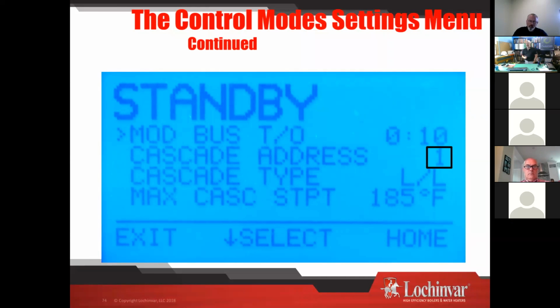Do you want to talk about Cascade? So Cascade is the ability to put multiple boilers together and let them work. So in my house, I actually cascade 2 small boilers. I have a 100,000 BTU load for my domestic hot water. I got a 35,000 BTU load for my space heating. In Massachusetts, where I am, you can collect 2 rebates. So you put 2 boilers in, they pay the rebate twice. So I put 2 50,000 BTU boilers, and I almost think I might take them out and put 2 new ones because they're like 7 years old, but the rebate's like $2,700 now. So definitely pay for the boilers. But so you do something like that, it becomes pretty lucrative for the homeowner in the day.